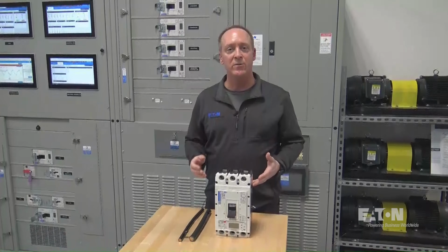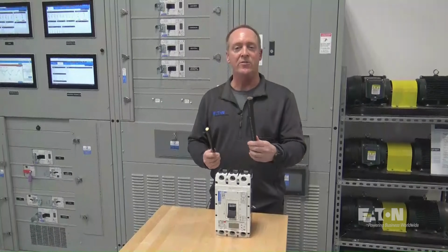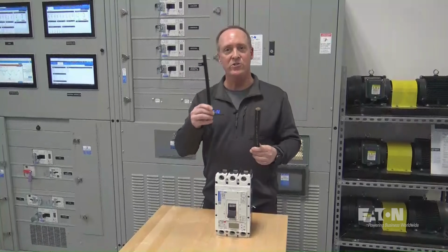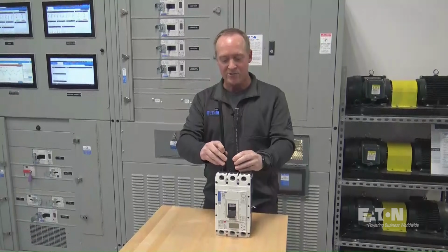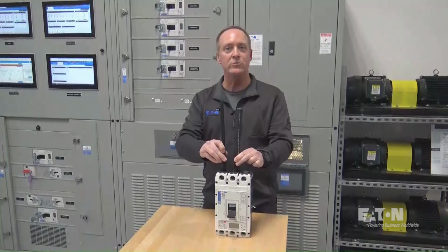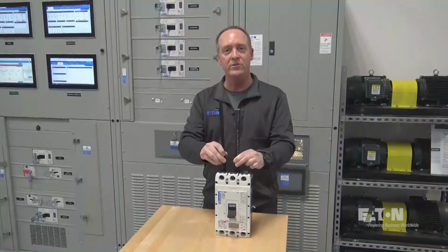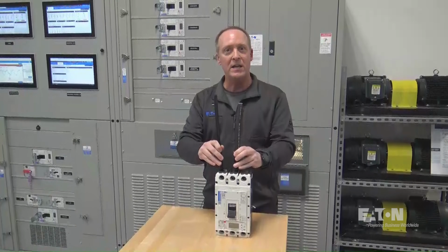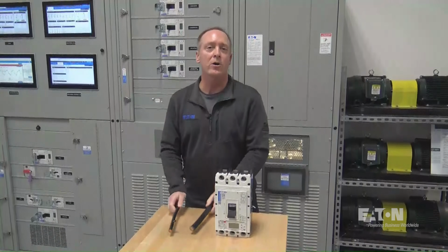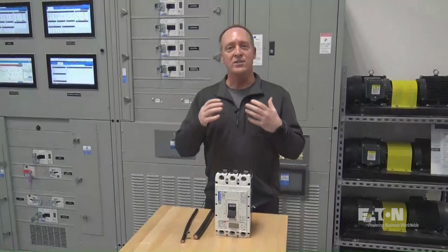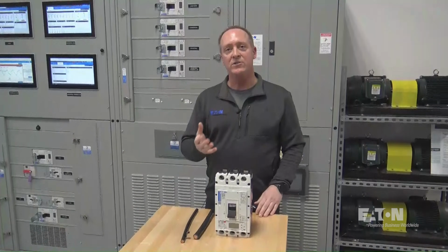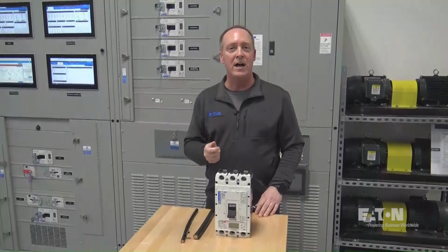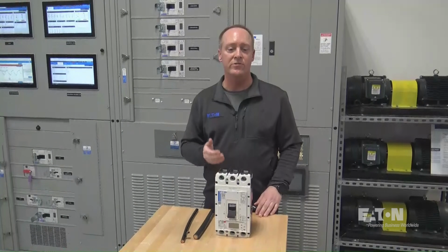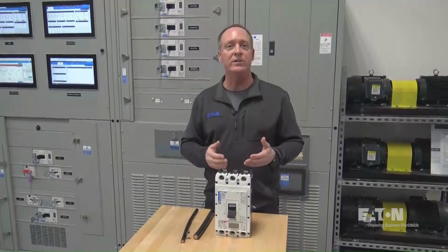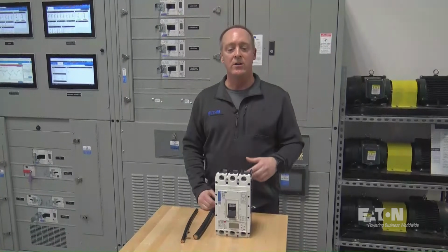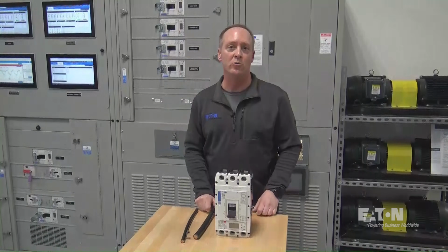So why is this significant? Well, you can think, let's say that this is a 125 amp rated cable versus a 100 amp rated cable. You can imagine the difference in terminating these two onto the circuit breaker, and what that does to the temperature of the termination and in the given enclosure. So 100% circuit breakers are tested with this in mind. They are tested with smaller cables that are only sized to 100% of the rated current in the circuit breaker, and then the temperature is checked against the UL temperature limits of the terminations and the given enclosure.